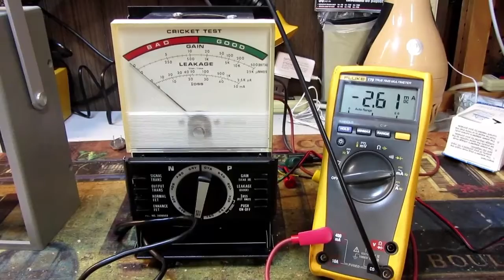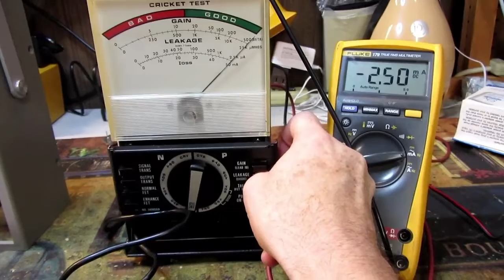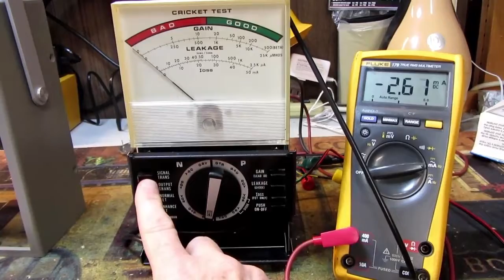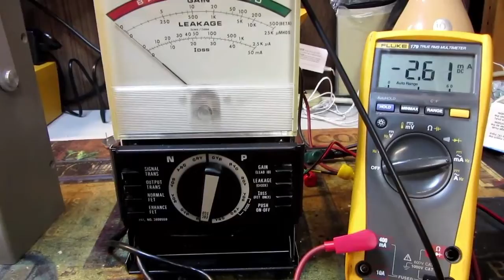After that, you're going to connect up, as they show in the service manual, you have to connect the resistance between the yellow and red test leads, in series with your DC milliammeter. At that point, when you engage the leakage test, it should be full scale with 2.5 mA, as you see here on my Fluke meter. When you perform this test, all of these switches on the left side should be in the out position. And the first calibration pot was the one at the far end here.